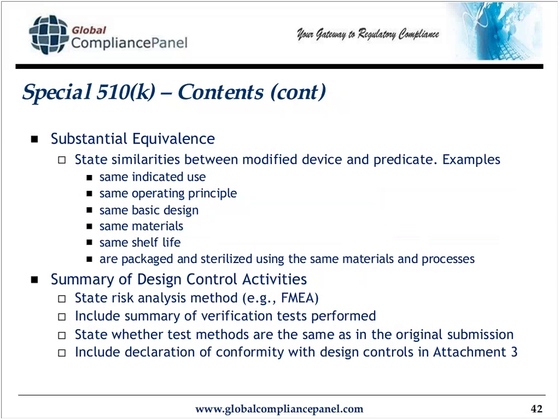Then I'm going to include a summary of the design control activities. I'm going to talk about the risk analysis method, perhaps a design FMEA or a process FMEA. I'm going to include a summary of the testing that was performed. When it says state whether test methods are the same as the original, I'm going to make sure that they're the same. Your goal during a special 510K is to have as little as different as possible. Any differences you're going to have to explain or test away.